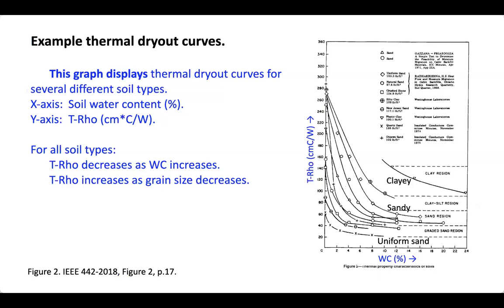Now, this is from the IEEE standard, and this table just shows some representative thermal dryout curves, and the water content of the soil sample is plotted on the x-axis, 0 on the left, which is perfectly dry, up to about 20% water content on the right. And the thermal resistivity rises up the y-axis. And you'll notice that the thermal dryout curve of a uniform sand has pretty low T rho values, whereas the clay curves are significantly higher, and then there's things in between.